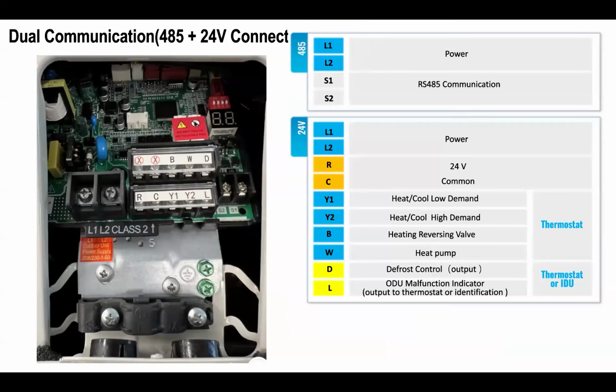R and C from the 24 volts to those terminals. They were immediately blowing the comm chip in the board. So those terminals have actually been moved. The two X's do nothing, and your S1 and S2 terminals are right here now. They've moved them away to try to keep people from screwing it up.